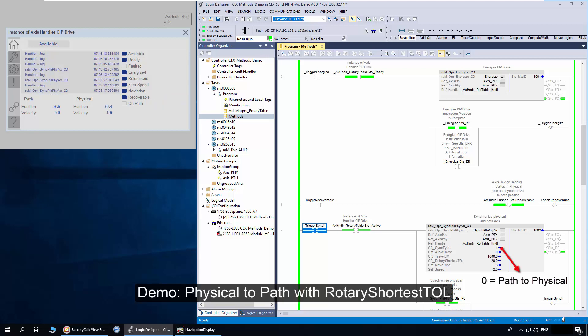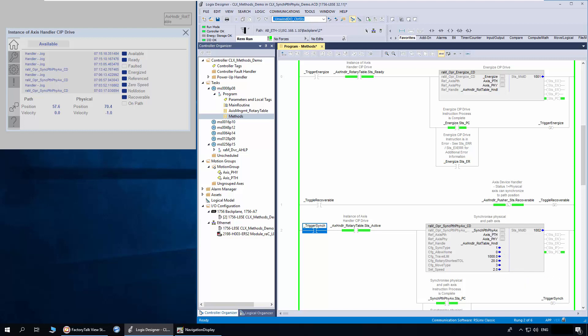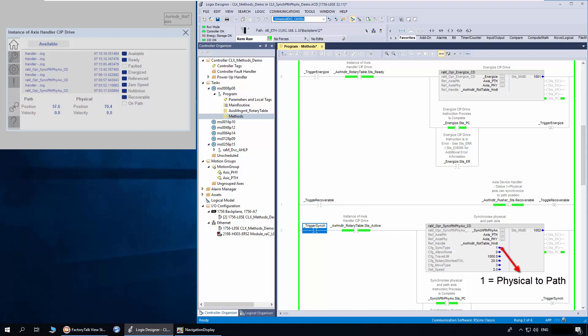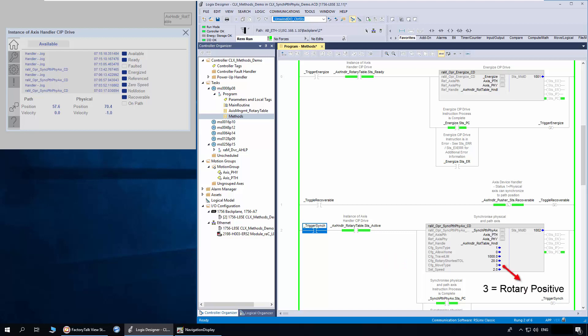Next I will demonstrate how rotary shortest travel limit works. In some applications, the axis mechanical movement is always allowed in one direction, but in case of a minimum recovery distance, the mechanical is allowed to move in reverse direction. For the demo, the physical axis is at 70 degrees and path axis is at 57. The sync type is set as 1. Rotary shortest TOL is set as 20, meaning if the recovery distance is within 20, the physical axis can do a rotary shortest move. Move type is set as rotary positive and set speed is at 2.